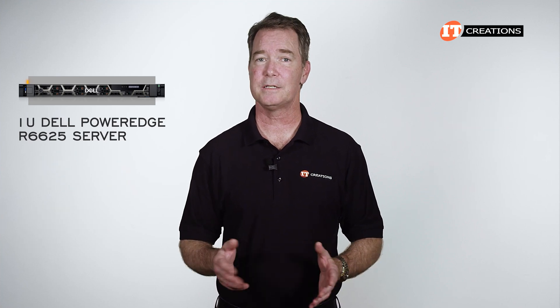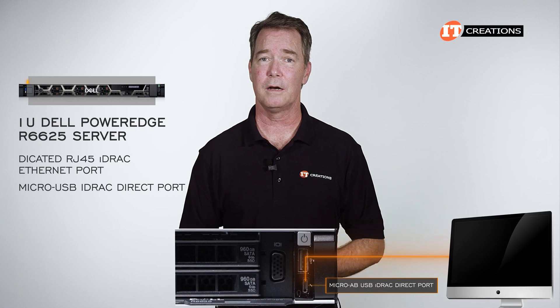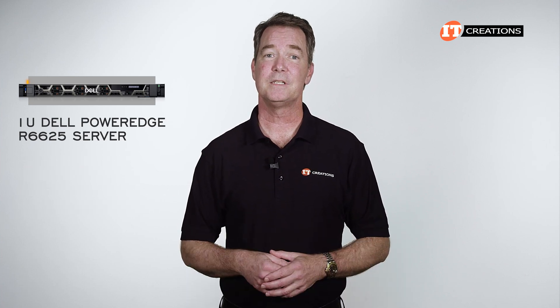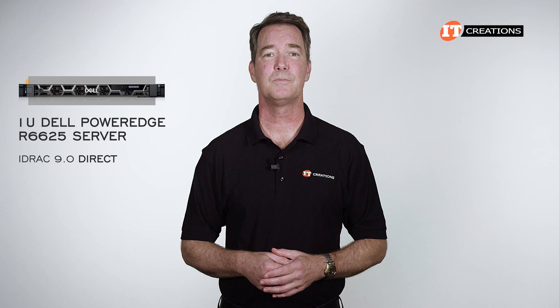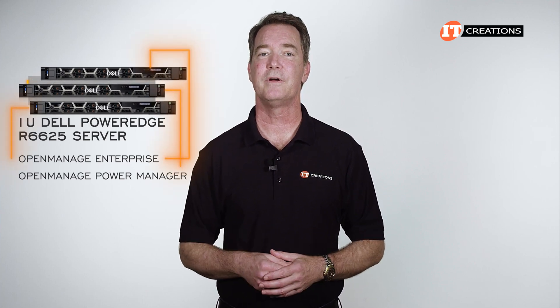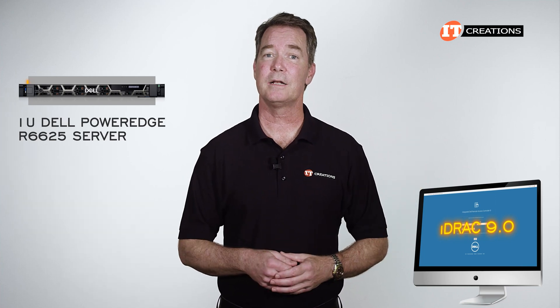There are several ways to manage the system at chassis or remotely: the dedicated RJ45 iDRAC Ethernet port on the back, the micro-USB iDRAC Direct port on the front-right server ear, and the optional QuickSync 2 — which enables you to access the system from a smartphone or tablet using the OpenManage mobile app. This system supports iDRAC 9.0 Direct, but can be upgraded to iDRAC Enterprise or Data Center. OpenManage Enterprise and OpenManage Power Manager can also be included for managing multiple systems.